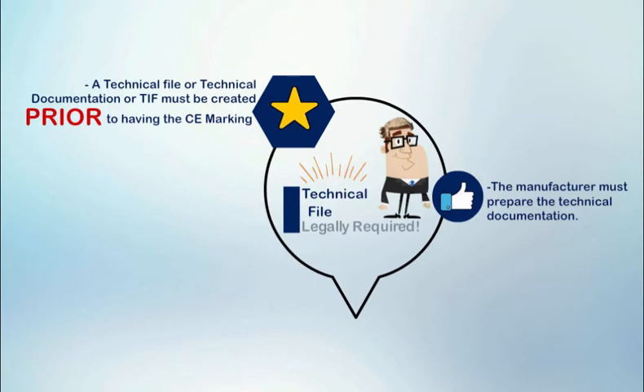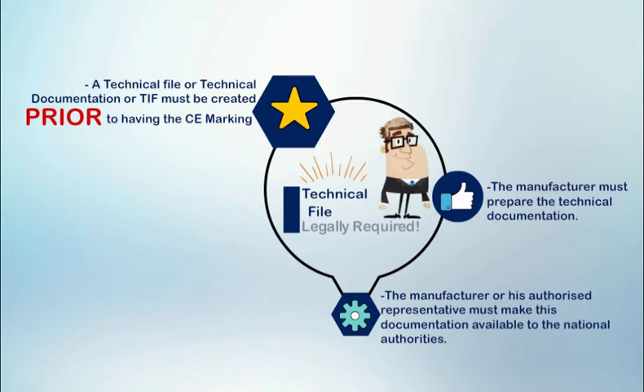The manufacturer must prepare the technical documentation described in Section 3. The manufacturer, or his authorized representative, must make this documentation, including the Declaration of Conformity, available to the national authorities for inspection purposes for a period ending at least 5 years after the last product has been manufactured. In the case of implantable devices, the period shall be at least 15 years after the last product has been manufactured.